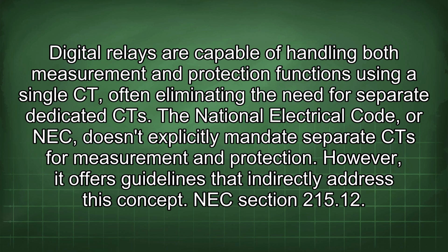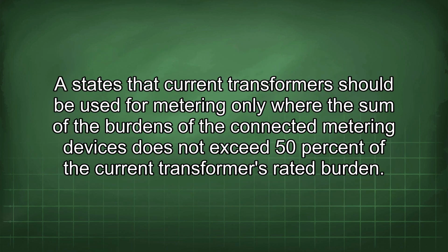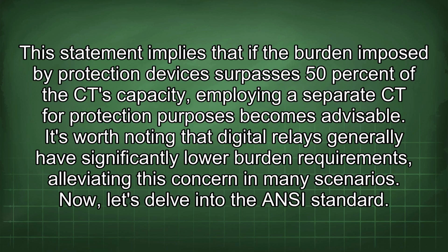NEC Section 215.12 states that current transformers should be used for metering only where the sum of the burdens of the connected metering devices does not exceed 50% of the current transformer's rated burden. This statement implies that if the burden imposed by protection devices passes 50% of the CT capacity, employing a separate CT for protection purposes becomes advisable. It's worth noting that digital relays generally have significantly lower burden requirements, alleviating this concern in many scenarios.